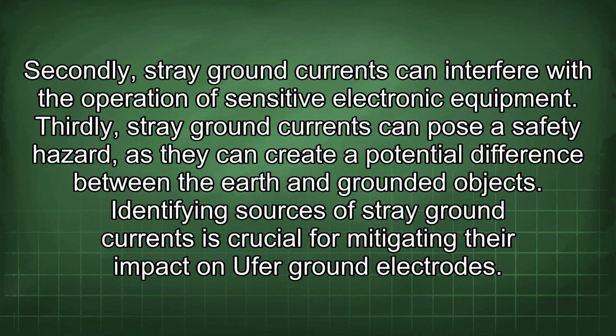Secondly, stray ground currents can interfere with the operation of sensitive electronic equipment. Thirdly, stray ground currents can pose a safety hazard, as they can create a potential difference between the earth and grounded objects. Identifying sources of stray ground currents is crucial for mitigating their impact on Ufer ground electrodes.